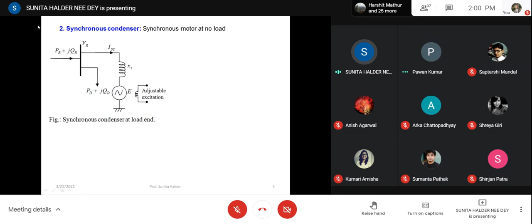Okay, so you have three options actually. SVC is also a kind of using a capacitor or inductor depending upon the load at the receiving end. Shunt capacitor and inductor are the compensating devices, but the synchronous condenser and SVC are similar. In the synchronous condenser, you control the excitation to get it in capacitive mode or inductive mode, and in SVC you control the current through the inductor.